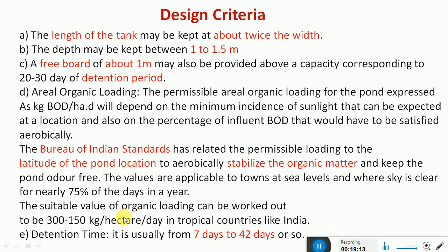So the strength of the waste is usually measured in terms of its BOD, and this is the load for tropical countries like India. If you go for colder countries, then the bacteria may not work that effectively, because bacteria also need certain temperature and atmospheric conditions for proper growth and development and to function effectively. So that's why for Indian conditions, the organic loading can be worked out at 300 to 150 kg per hectare per day.